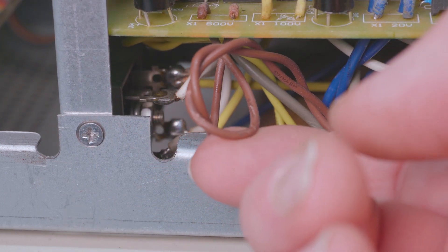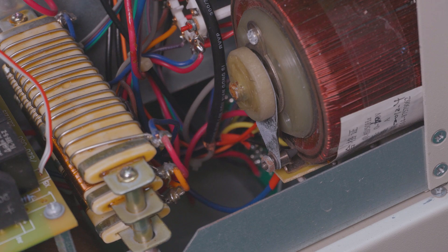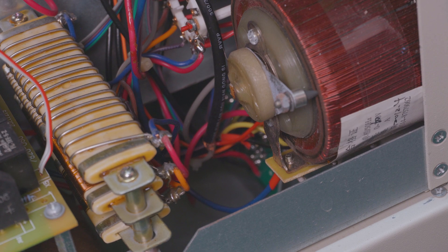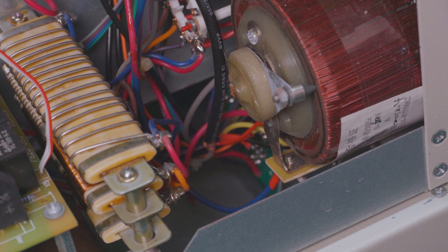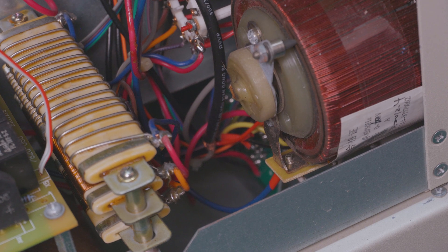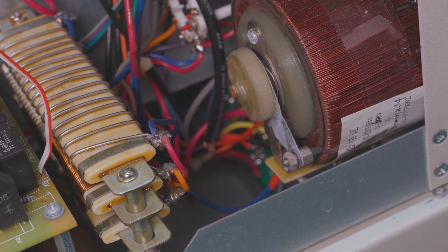Looks like these wires labelled 500 volts have been chafing on that sharp metal. Nice one. And here up the front we've got our variable transformer and there's quite a bit of corrosion on that wiper arm and there seems to be a little bit of flex in it too.